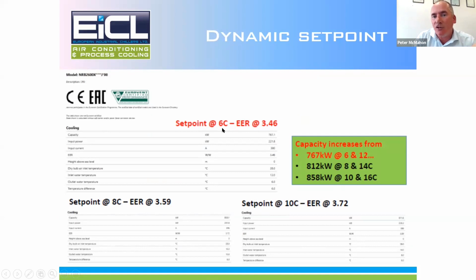So for example, at 6 degrees C here, supply temperature, we have an EER of 3.46 and 767 kilowatts. If we increase that to 8 degrees, keeping the same delta T, same flow rate, you can see that increases to 812 kilowatts on the same unit with a greater efficiency, 3.59. So this is what you get out versus what you put in, remember. If we increase our set point to 10 degrees, it increases capacity to 858 and the energy efficiency ratio to 3.72. So straight away, you can see the benefits of increasing our set point.